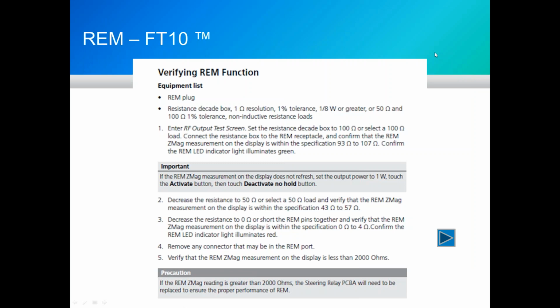So let's minimize that screen for now. And we're back to that overall test screen. So just recapping, set 100 ohms, our range is 93 to 107. Set for 50 ohms, our range is 43 to 57. Short them together, should be somewhere between 0 to 4 ohms, and we were 1.7 or so. And then again, an open circuit, we want to see something less than 2000 ohms.